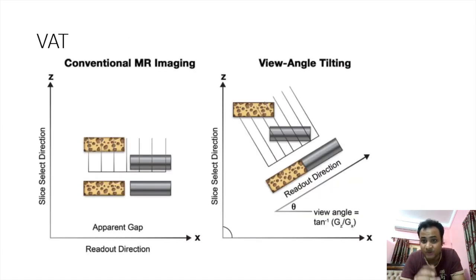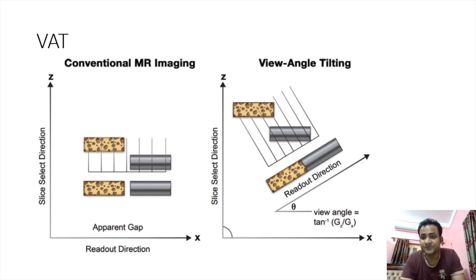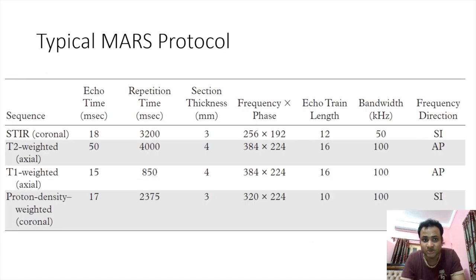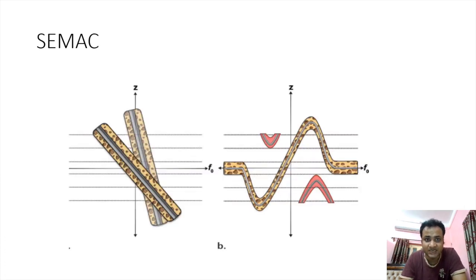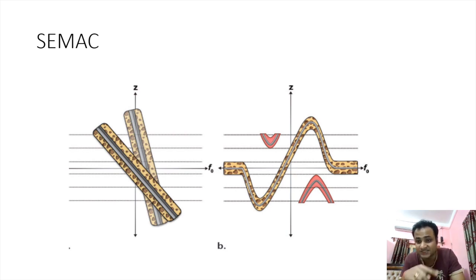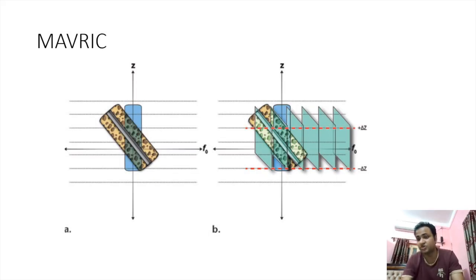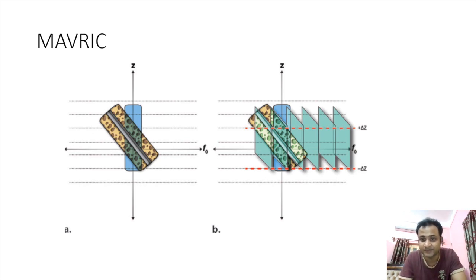There are special sequences for metal artifact reduction: VAT (View Angle Tilting), where the readout direction is altered so that view angle tilting helps reduce artifacts from metallic prostheses. MARS protocol provides an overall tabular representation of sequences and timings. SEMAC (Slice Encoding for Metal Artifact Correction) is another technique that changes the frequency encoding direction and alters the readout gradient to reduce artifacts. MAVRIC is a similar technique that reduces artifacts in the frequency encoding direction by providing repeated excitations read out rapidly.